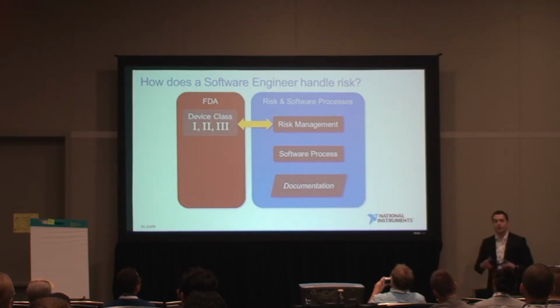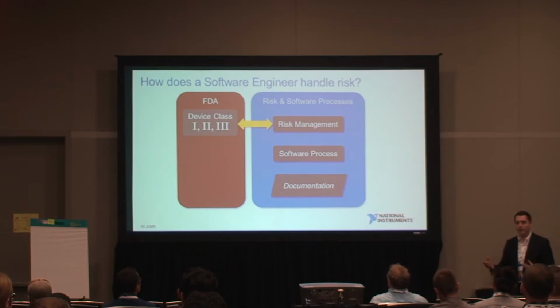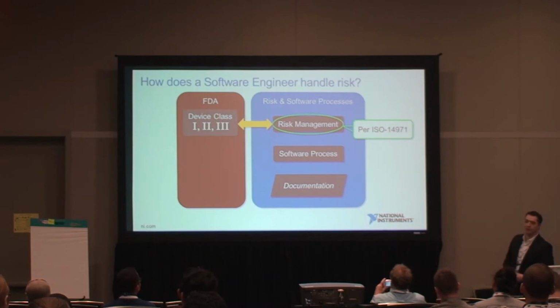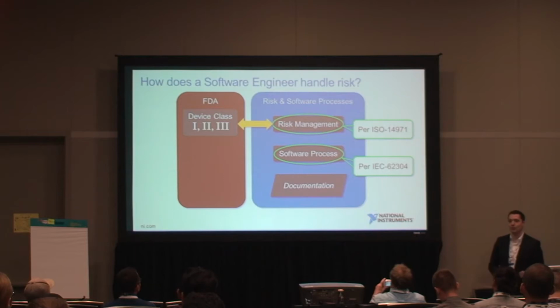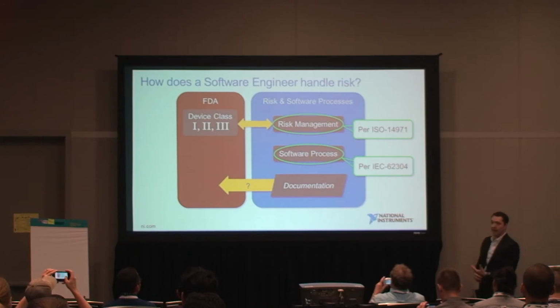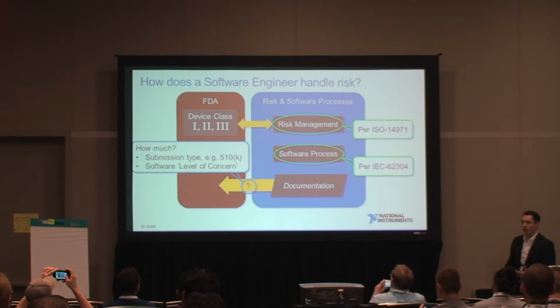And through the whole thing, because we're good engineers, we have a documentation process, we're producing documentation. So risk management will do that. The consensus standard for that is ISO 14971. For software, IEC 62304, which I'll touch on in a sec. And the question people ask a lot is, well, how much do I send to the FDA? What do they look at? Are they like looking through my LabVIEW code, right? No, first of all, not looking through the code.